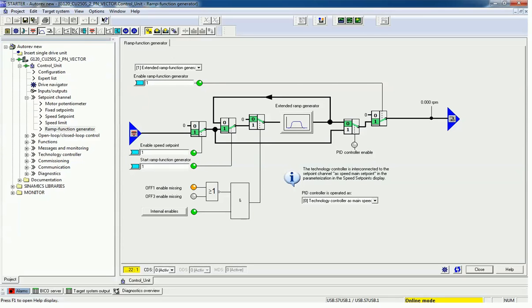In some applications like metro trains where we use traction motors, or in blower and crane applications, the load is variable. According to the load we need to give the ramp up and ramp down time. Sometimes we feel a jerk while the motor is reaching maximum speed or going from maximum speed to zero. To avoid that jerk we use a ramp function generator.